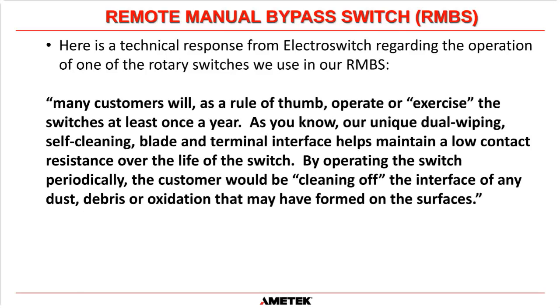So, you know, if you go back to that relay contact picture that we showed you, whenever you move that RMBS from one position to another, there is going to be arcing. And what ElectroSwitch are saying is when you move those switches, there is a self-cleaning action, a wiper that helps keep the surfaces clean. And if you don't operate that switch, then what happens is, most of the time the RMBS is going to be in the normal position. That's the way that it should be.